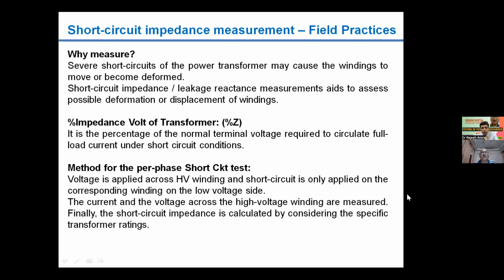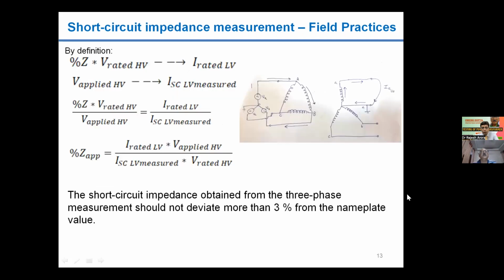Finally, the short circuit impedance is calculated by considering the specific transformer rating. On the next slide, we will show you the formula to estimate the percentage impedance. Though the percentage impedance that we are estimating through this method may not be exact according to the design parameter, it gives approximately near to that.